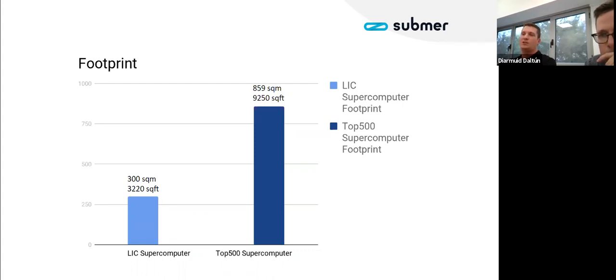So this is just challenging that difference in rack density versus the traditional approach. So, for example, in the case of Summit, it uses a footprint of 860 square meters, just under 10,000 square feet. We could deploy the same amount of compute, those 10 megawatts of IT compute, in just under 300 square meters or 3,200 square foot.